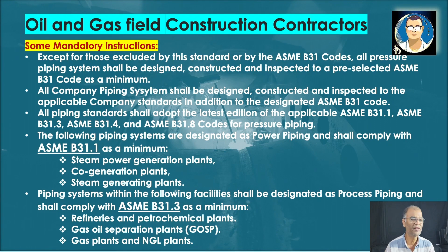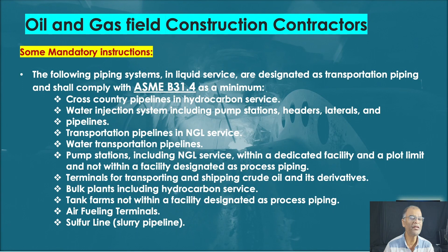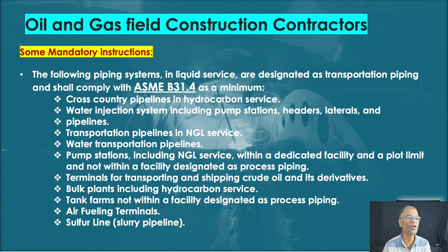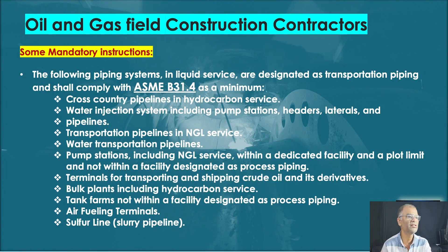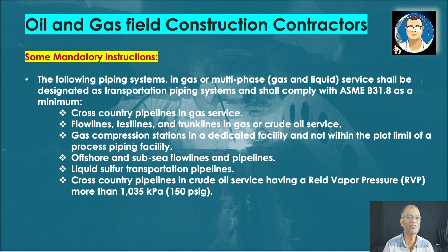Piping systems designed and constructed per B31.3 include refineries and petrochemical plants, gas-oil separation plants, gas plants, and NGL plants. Piping systems complying with ASME B31.4 include cross-country pipelines in hydrocarbon service, water injection systems including pump station headers and laterals, transportation pipelines in NGL service, water transportation pipelines, pump stations within a dedicated facility and within the plot limit but not designated as process piping, terminals for transporting and shipping crude oil and products, bulk plants including hydrocarbon service tank farms not designated as process piping, air fueling terminals, and sulfur lines.